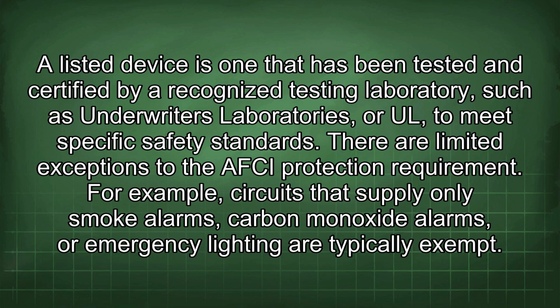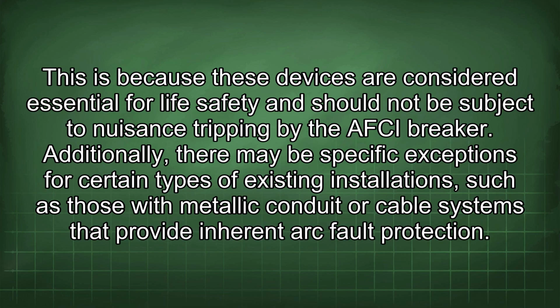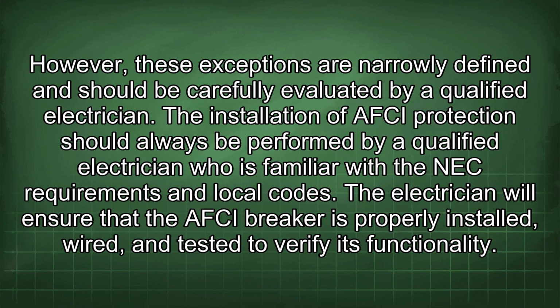There are limited exceptions to the AFCI protection requirement. For example, circuits that supply only smoke alarms, carbon monoxide alarms, or emergency lighting are typically exempt. This is because these devices are considered essential for life safety and should not be subject to nuisance tripping by the AFCI breaker. Additionally, there may be specific exceptions for certain types of existing installations, such as those with metallic conduit or cable systems that provide inherent arc fault protection. However, these exceptions are narrowly defined and should be carefully evaluated by a qualified electrician.